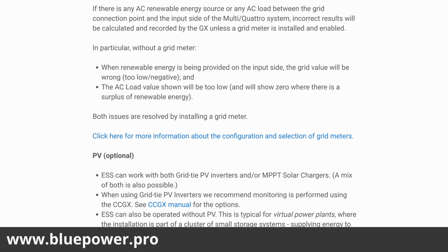If there is any AC source between the AC input from the grid and the solar system, incorrect results will be calculated and recorded by the GX device unless a grid meter is installed and enabled. So if you have a PV inverter on the input, it's also going to interfere with the readings from your Victron system. In particular, without a grid meter, when renewable energy is being provided on the input side, the grid value will be wrong, too low or negative. The AC value will also be shown too low on the output side.